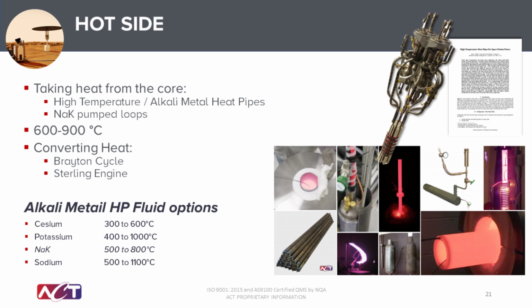Looking at a couple of technologies on the hot side, this leverages a lot of our work done for Kilopower, but we also make these high temperature heat pipes for a lot of terrestrial use. We have a pretty routine line called isothermal furnace liners used in calibration equipment across national labs around the globe. At its core it's a heat pipe, but it uses liquid metal as the working fluid and superalloys or stainless steel as the envelope material.